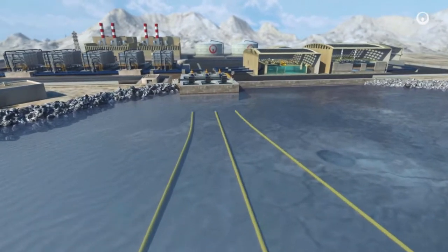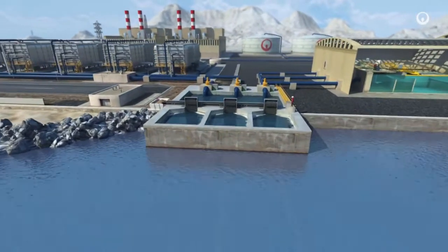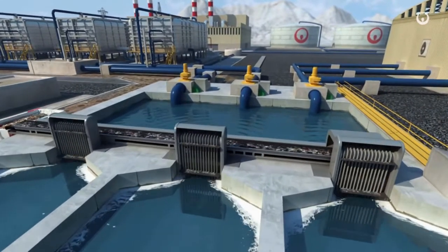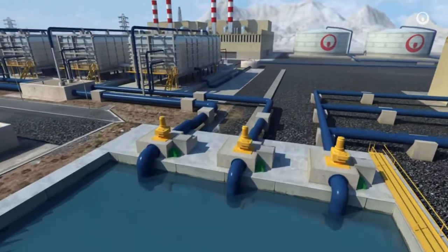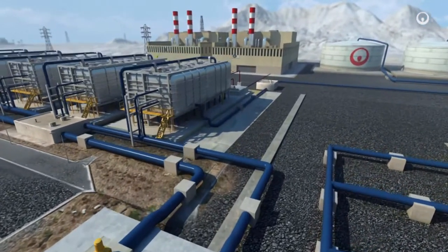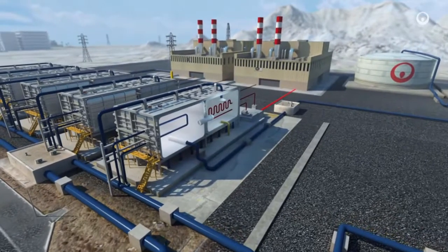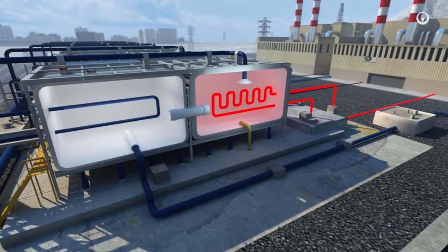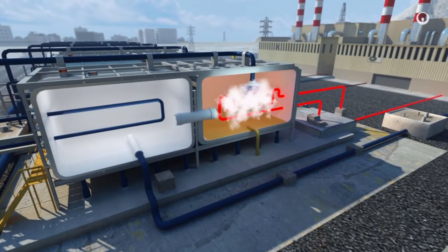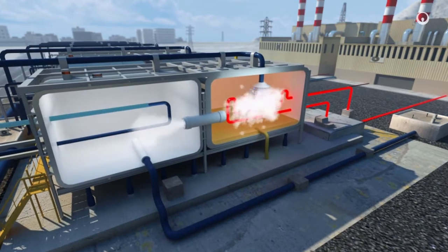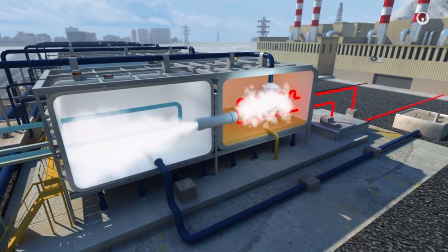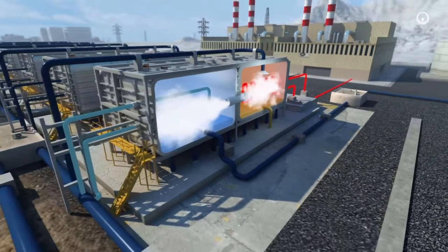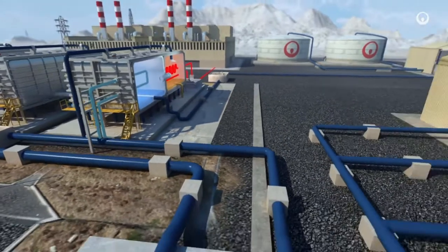We extract seawater several hundred meters offshore. Gratings in screens block large floating objects and keep sea life out. We desalinate some of the seawater by distillation. This technology reuses steam from a close-by thermal power plant that would otherwise be wasted. The steam evaporates the seawater to separate it from the salts and other substances. The steam then moves into cooled pipes and the fresh water condenses. The rest of the seawater heads into the reverse osmosis desalination unit.